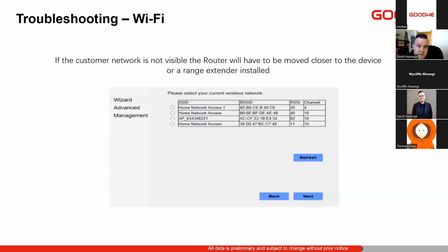Next, we can check to see that the device is visible from the app configuration or from the web interface configuration. I prefer the web interface because we have a nice numerical view of the signal strength. Always important to make sure this is above 40% signal strength. Even 40% sometimes, if there's a lot of interference between the inverter and the Wi-Fi, can cause it to drop off regularly.